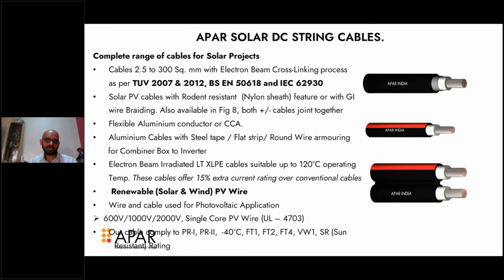We also offer this generally, like we said, for aluminum and copper, the price difference being high, as a flexible aluminum conductor, or it could be copper clad. It's an aluminum conductor with a copper clad done on that. And the DC underground we can offer with round wiring, flat strip, or all steel tape armoring, depending on the requirement. But those are generally from the combiner box to inverter. These single core cables, which are used for the panels, are generally suitable for 120 degrees operating, and they offer 15% more current rating than normal cables.